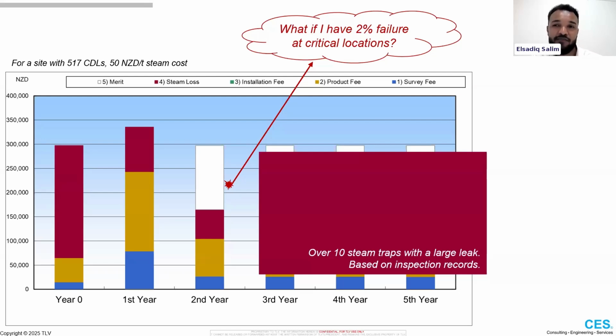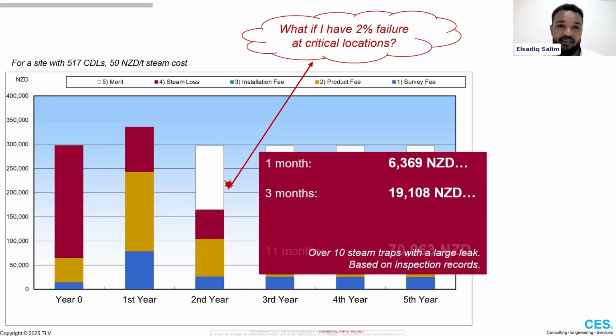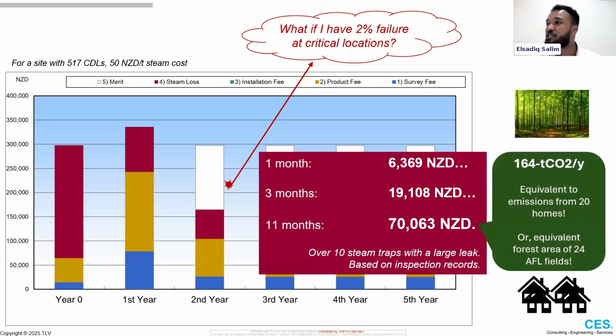Critical locations have failed right after their second year steam trap survey. Based on calculations, after 1 month, those 10 steam traps have cost about $6,000. 3 months, just under $20,000. And just before their next survey, they've already lost $70,000 over just that 2% failure, just those critical steam traps with large leakage losses. To put it in terms of emissions, that's 164 tons of CO2 equivalent, 10 steam traps, equivalent to the energy that 20 homes would use, the emissions of 20 homes. So it's quite sad when you look at it like that, 10 steam traps. So there needs to be some solution for these critical locations that we cannot afford to leave for a full year.